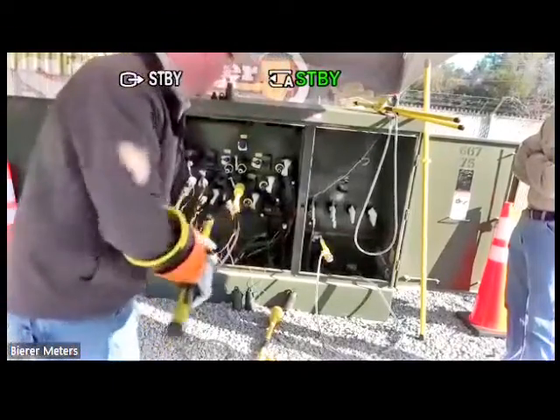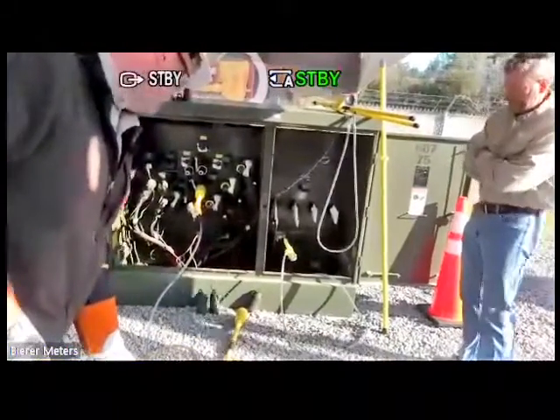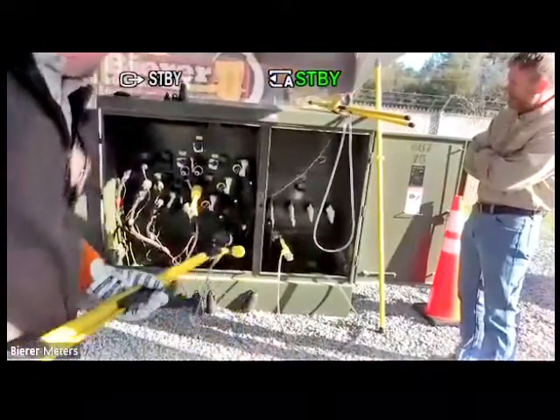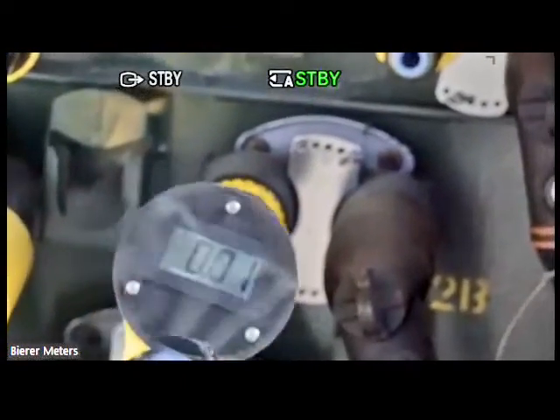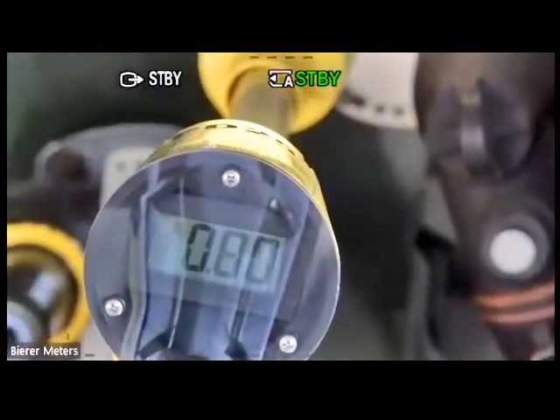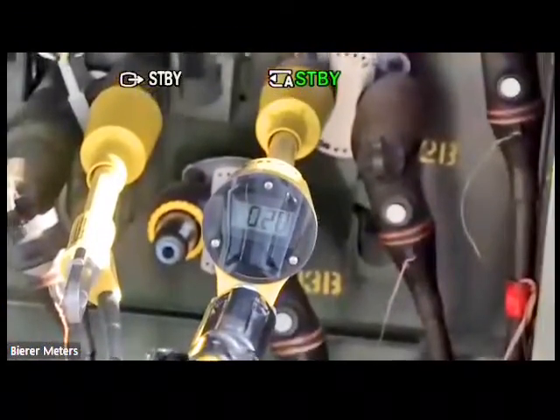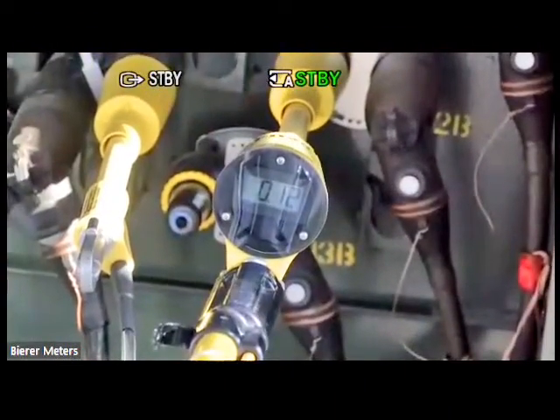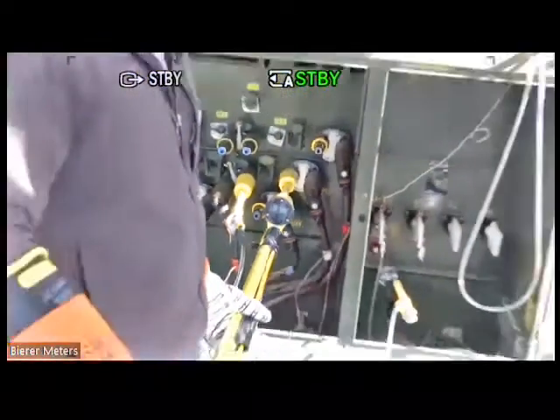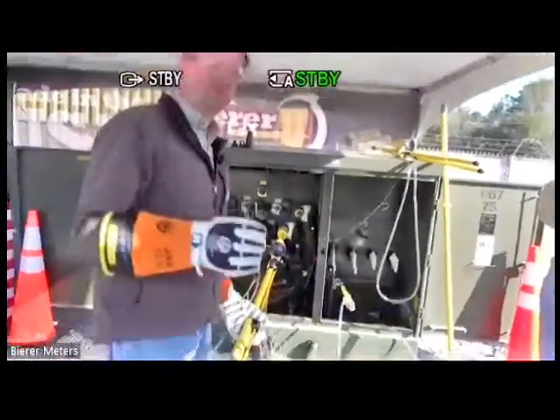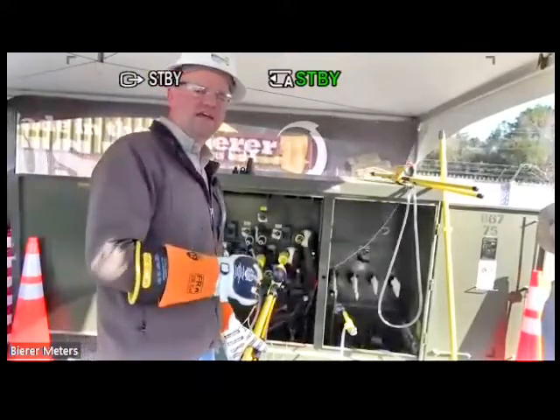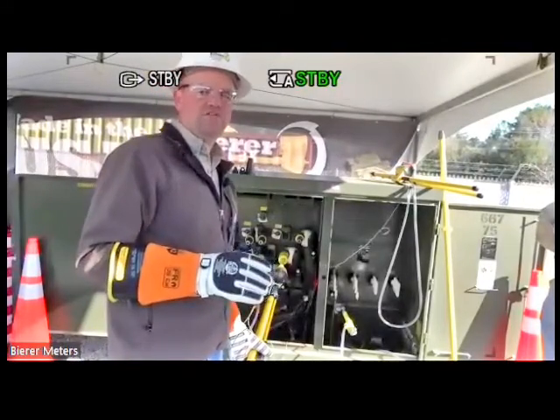Okay. Then I want to take this meter probe again and put it on my source. And I'll get Ryan to kind of focus in on this housing before I insert it, just so you see that number kind of jump up. Ready? See that number jump up? So it jumped up around 5 kV, almost 6 kV, and there it goes right back down to near 0. Okay. So you see that potential being inserted into that de-energized cable, and you should see that number bleed off.